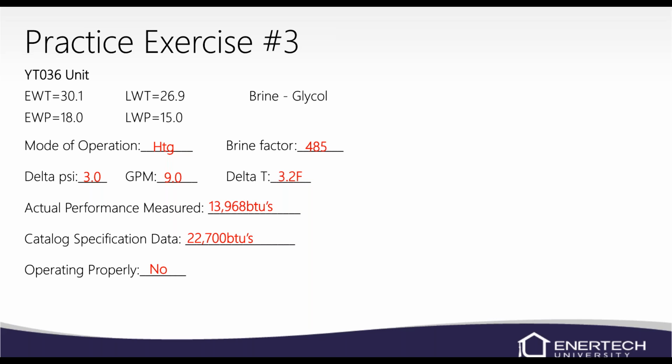But this is just an example I can bring up because over time, working with equipment, you'll start to realize, hey, that's 2/3 capacity. I wonder if it's upstaging. So heat of extraction is the first diagnostic tool that we should be using on all equipment. But again, make sure you have airflow and water flow first, because we can't expect those calculations to be proper until those two flows are established.